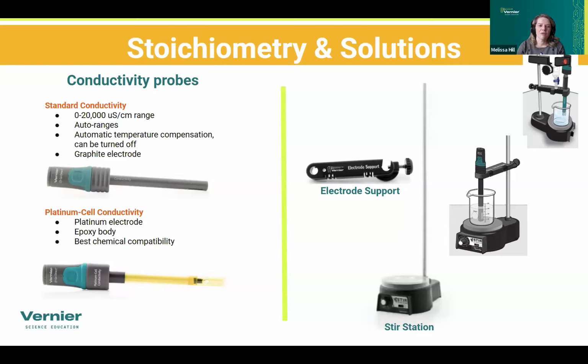So that's why we came out with the platinum cell conductivity probe. Not only does it have all the same things that the standard one does, that 0 to 20,000 range, the auto ranging, and all the 3 sensor channels, but it has a platinum electrode in it, so it's better at handling those quick polarizations. And it has an epoxy body, so it has much better chemical compatibility. And you'll see that as a theme in a lot of the chemistry sensors. All of them have similar specifications, but the chemical compatibility gets better, or just different, with the different versions.